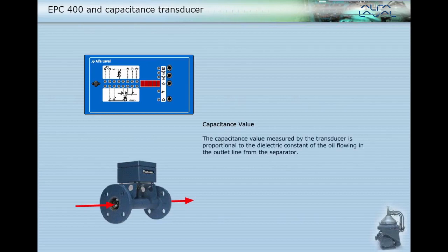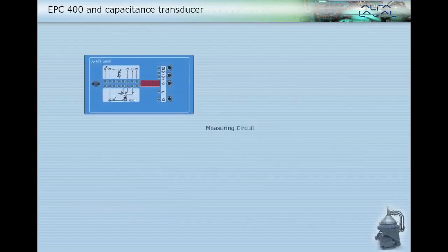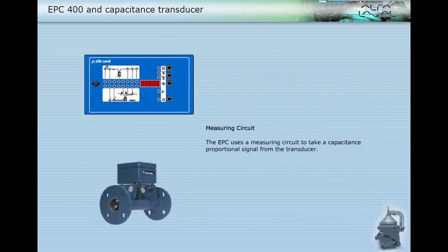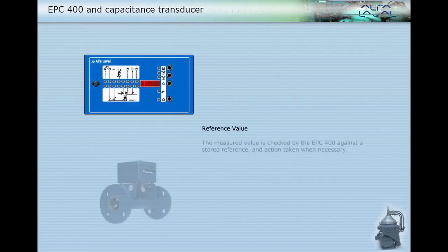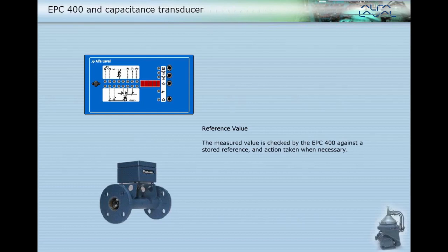The capacitance value measured by the transducer is proportional to the dielectric constant of the oil flowing in the outlet line from the separator. The EPC uses a measuring circuit to take a capacitance proportional signal from the transducer. The measured value is checked by the EPC 400 against a stored reference and action taken when necessary.